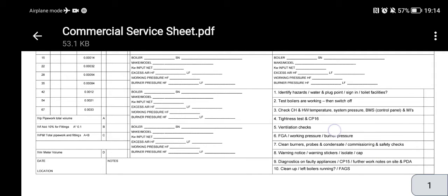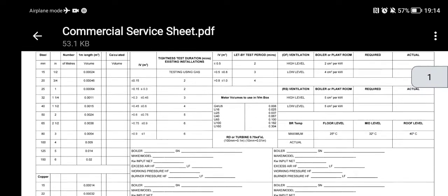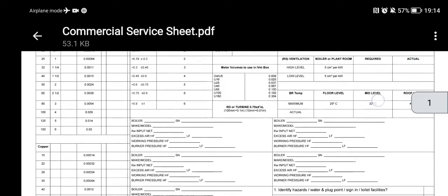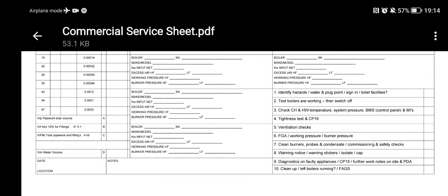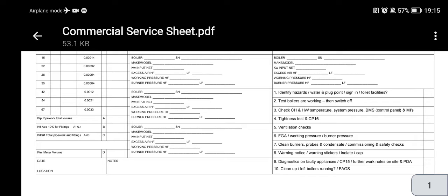Then ventilation checks — see how much ventilation the plant room has, start writing out your ventilation details on the sheet, and write your plant room temperatures. Once that's done, turn a boiler on and carry out flue gas analysis. Whilst you're doing that, have your gauge connected and check your burner pressure at the same time — in high rate and low rate.